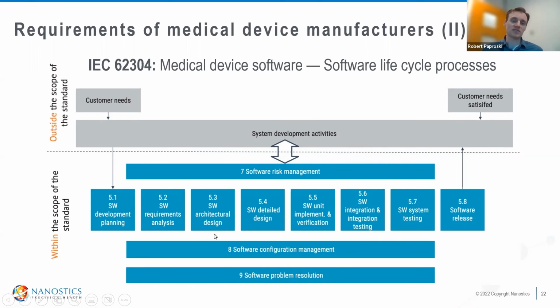If your medical device is a higher class and higher risk, you may have to come up with architectural diagrams and detailed design information, which can include describing the entirety of what all the different classes of your software are, what the different methods, functions, parameters and default values are, and it all needs to be written out. It's quite a bit of work. And then there's the aspect of testing your software, unit testing, integration testing. This is more so to make sure that what you said in your detailed design and architectural diagram works as intended.